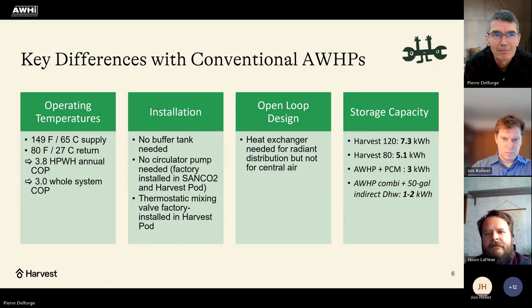Yeah, thank you, Jason. It is key that we do stratified storage. It is highly stratified, and the reason for that is to be able to get the storage density that we have on this slide. The storage capacity is the product of volume and temperature delta across the discharge of the delivery system, and by being able to use a 70-degree temperature delta or somewhere around there, and 120 gallons, that's how we can achieve this. If we were doing a mixed tank, it depends what temperature delta we'd have across the delivery system, but we would not be able to have the efficiency and the speed of recharge that we get with the system.